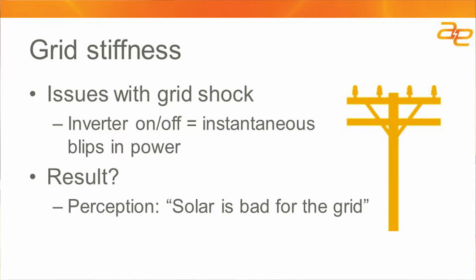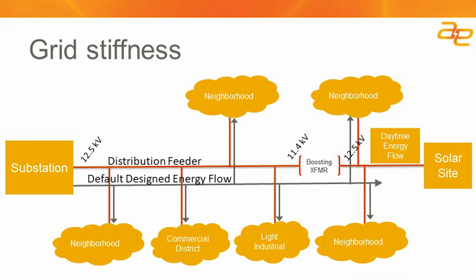So this concept that solar is bad for the grid, that you hear a lot on the news, it's actually fundamentally not true. And from the studies that we've been publishing through the years from my time with previous employers and through the NREL, we've got some real good data that shows that solar can actually be very helpful to the grid. So the issue of grid stiffness occurs based on design of energy flow from transmission lines through a substation and then out through a distribution feeder to neighborhoods and commercial buildings and all of the consumers of electricity. It was designed that way 100 years ago, and it wasn't designed with this concept of a source of energy existing down that line, that distribution feeder.